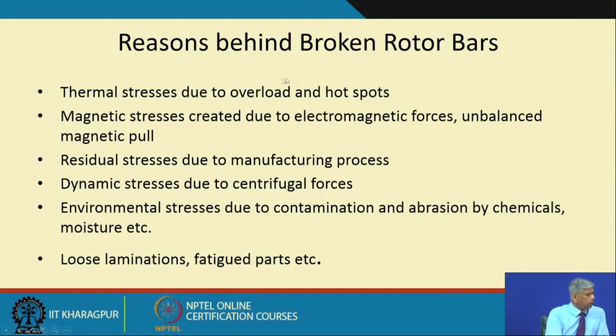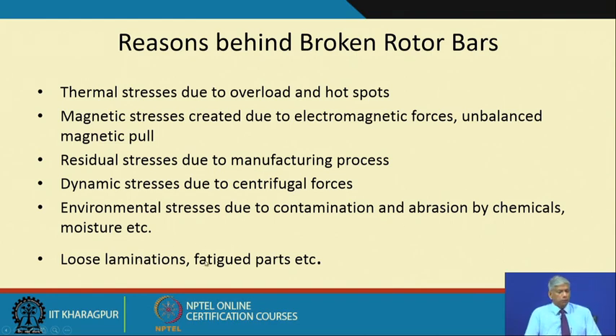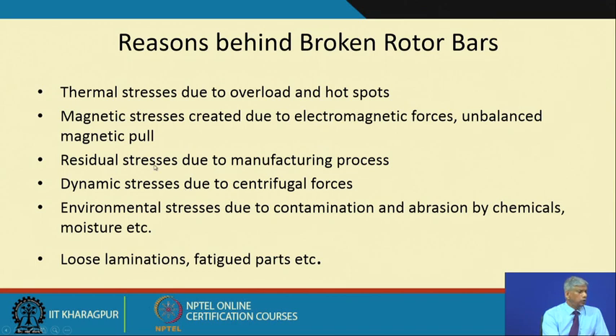Reasons behind broken rotor bars include: thermal stresses due to overloads and hot spots, magnetic stresses from electromagnetic forces and unbalanced magnetic pull, residual stresses from the manufacturing process, dynamic stresses due to centrifugal forces, environmental stresses from contamination and abrasion by chemicals and moisture, loose laminations, and fatigue. Residual stresses from manufacturing could influence the resistance and related characteristics of the motor.